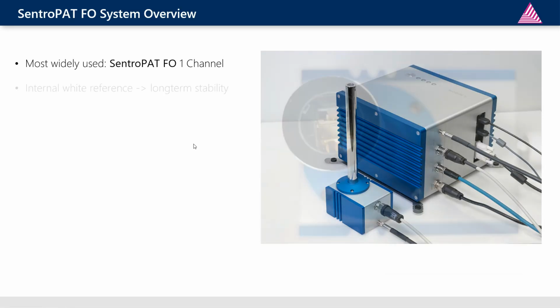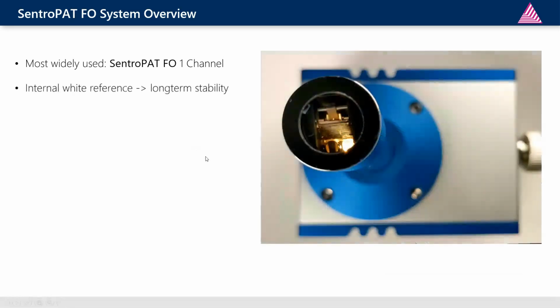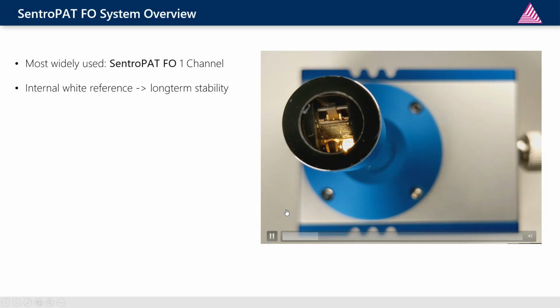Let's have a look into the central probe, the RLS. When you take a look into the tip, you see two rods here. These are the two light sources. One is just illuminated, the other is not. Then you see here the internal reference, which is one of the most important features of the systems. It flips on a time-controlled base, measures an internal white reference, and goes back to measurement position. And so it allows to correct the complete system for long-term or drift effects from temperature or from long-term changes over lifetime of the probe and for very long periods.